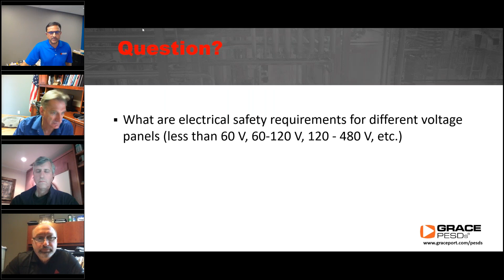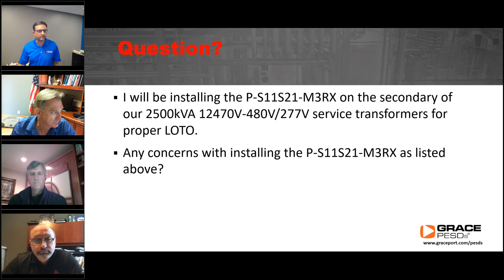We'll get to as many questions as possible. This one is a product related question: I'll be installing a PS11S21 M3RX. This is a voltage test station, shown in one of the handouts we provided. It can be used for electrical lockout tagout, with a combination of voltage presence indicator and a safe test point to verify absence of voltage from outside the door, with a max fault current of about 2.35 milliamps, as I recall. Look for that information in the product handout provided with the webinar.